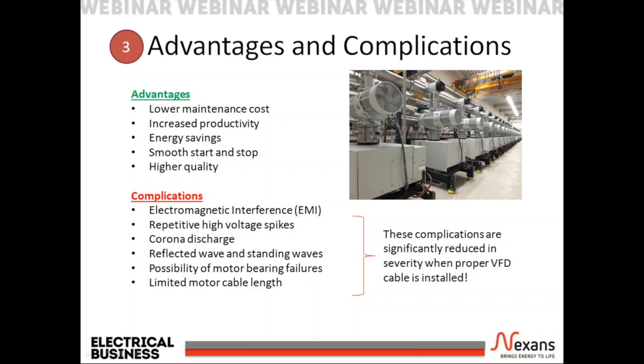Reflected wave and standing waves due to a difference in impedance between the cable and the motor. Under certain conditions, a pulse from the VFD can add to a pulse reflected back from the motor, resulting in a standing waveform. Possibility of motor bearing failures due to return currents not using the cable as the return path. Limited motor cable length, forcing the VFD to be installed very close to the motor, which may be impractical. If you don't use a proper VFD cable, these complications will cause failures in this and other systems. EMI is a great example of this.